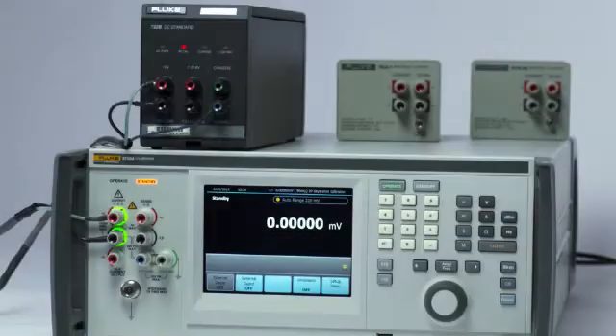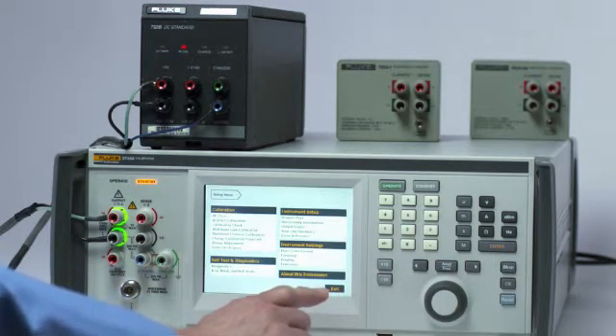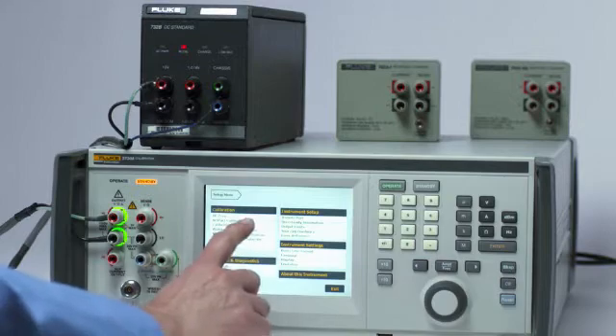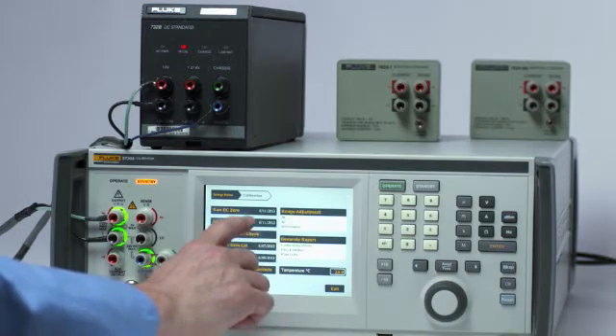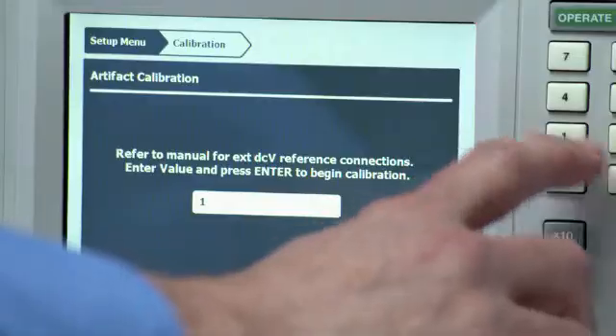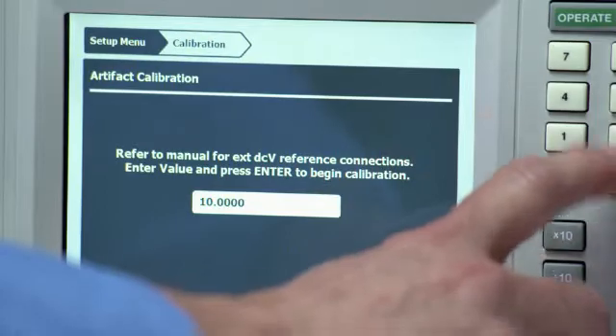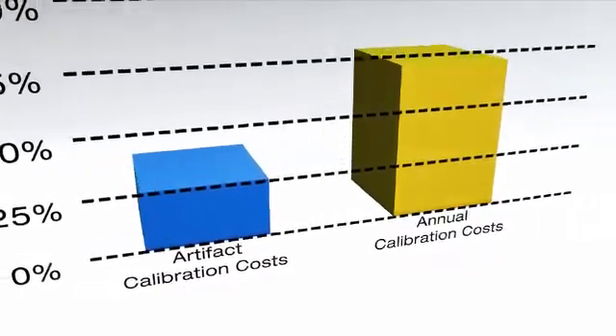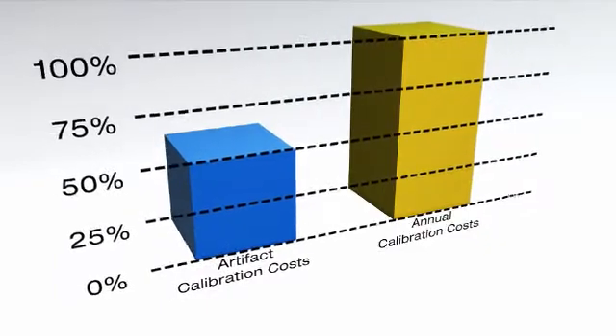The 5730A features artifact calibration to help you increase confidence and reduce cost of ownership. With just three standards, you can transfer external traceable values to the 5730A calibrator. At that point, it measures, verifies, and adjusts itself, reducing an eight-hour job to about one hour. Artifact calibration allows you to extend your calibration cycle up to two years before sending it to an accredited Fluke service center for a full verification.